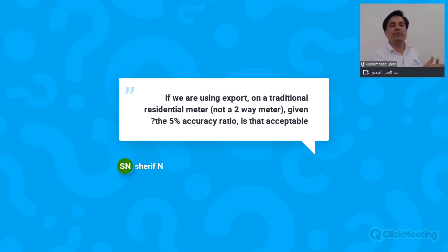So you have to be speaking to your grid authority about what is the latency period that is acceptable for your PV plant. As I mentioned earlier, the response time from a smart logger or the inverter itself is around 2 seconds. So your grid authority should be basing their approval on the response time that our inverter or smart logger has. So the accuracy is much better than 5% in case of the zero export.